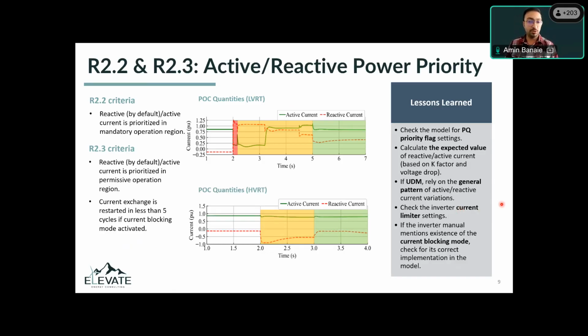Then talking about R2.2 and R2.3, these requirements are about active and reactive power priority. One thing about these is that in PRC-29, in the language of R2.2 and R2.3, it talks about active and reactive power, while the technical rationale document talks about active and reactive current priority. So it caused a bit of confusion for us on which parameters we need to investigate and monitor. Since in the rationale document it's mentioned several times that PRC-29 is moving along the IEEE 2800 standard, we went with the active and reactive current priority mode.